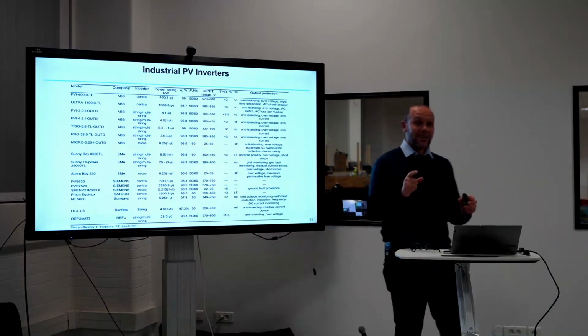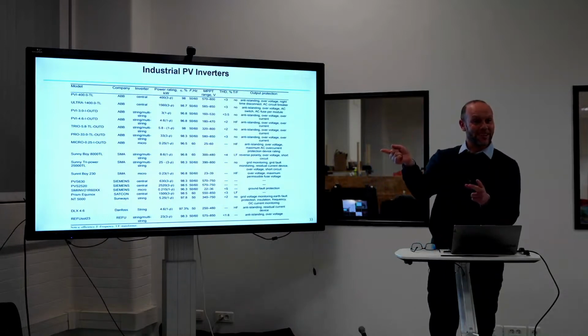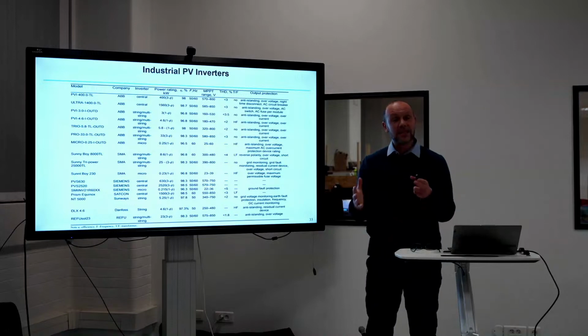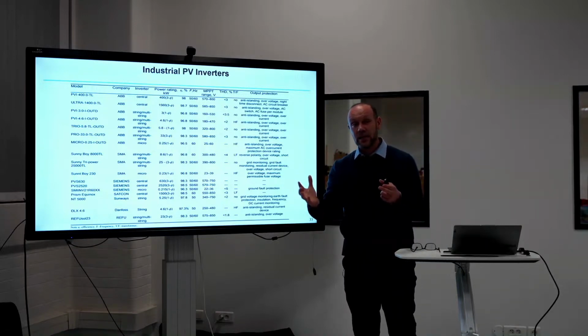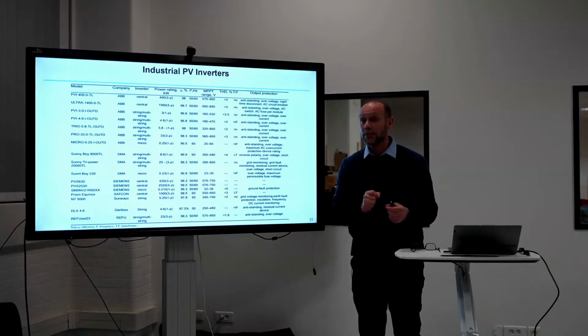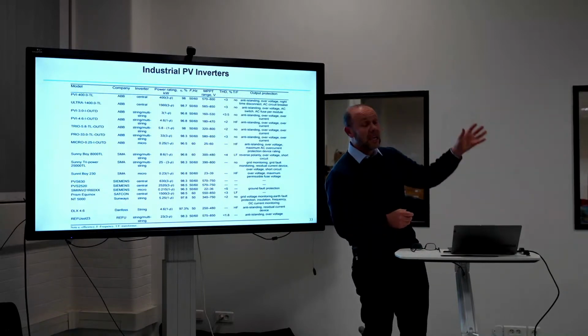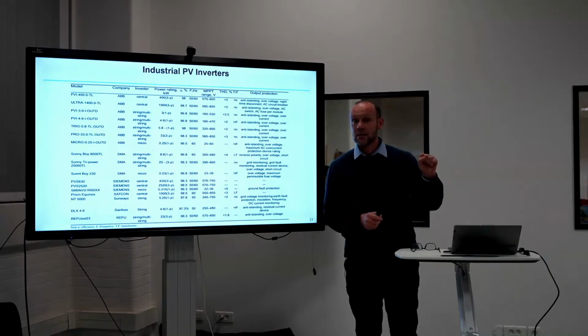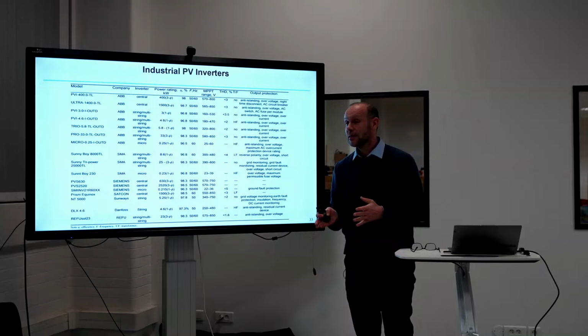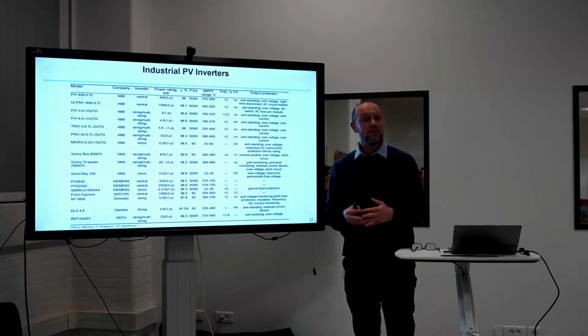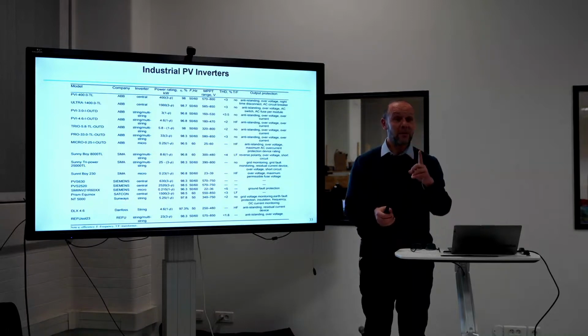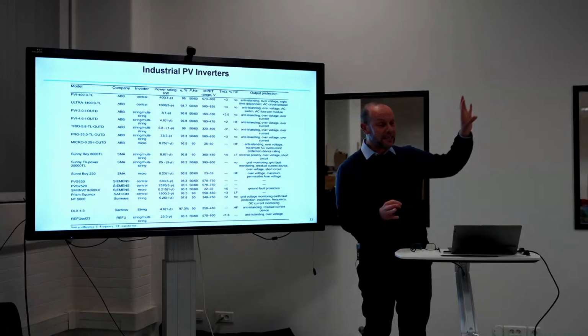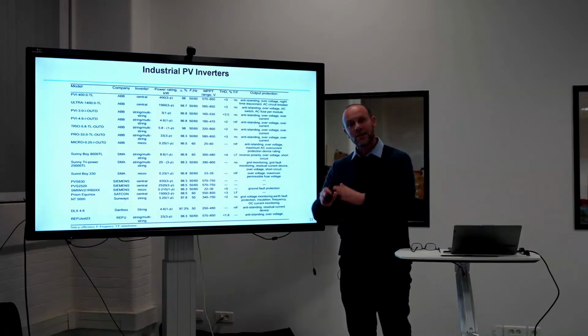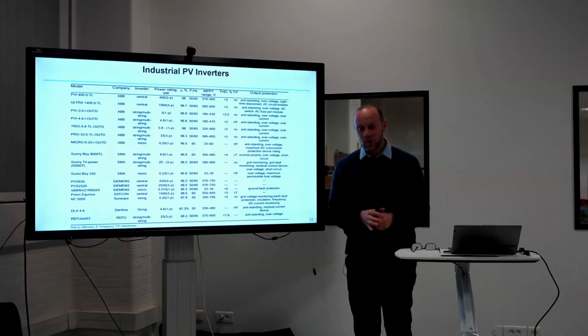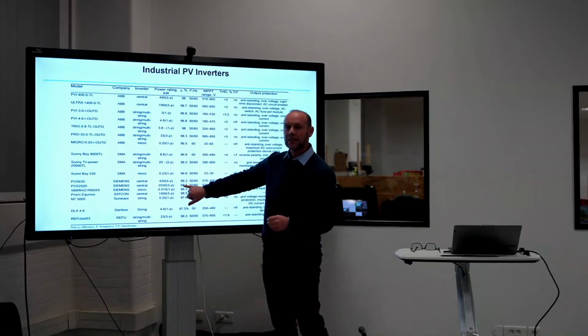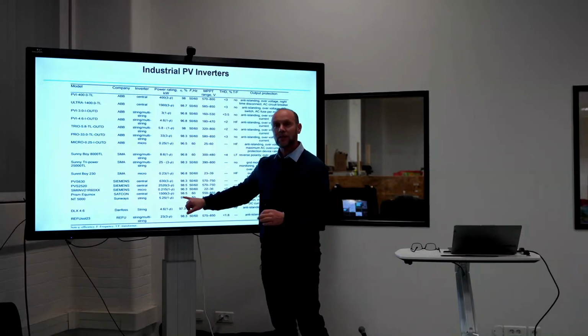Because in an inverter there is an efficiency curve. And that's why inverter sizing is a very important point when we design inverters and PV systems. For example, if you have 10 kilowatt peak PV panels, what is the inverter size? The inverter size may be 5 kilowatt, not 10, because that is 10 kilowatt peak, meaning at STC, the standard test conditions, in a perfect environment with no losses. So if your inverter is not operating at its operating point, you will never get this efficiency, maybe you get 50%.